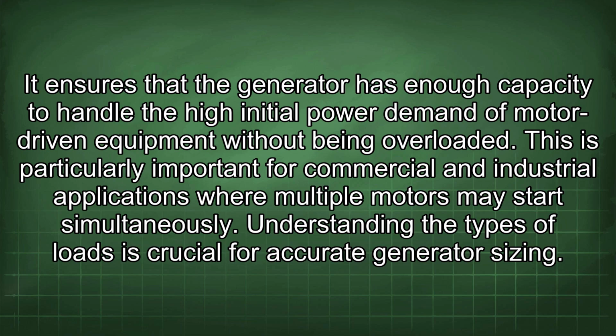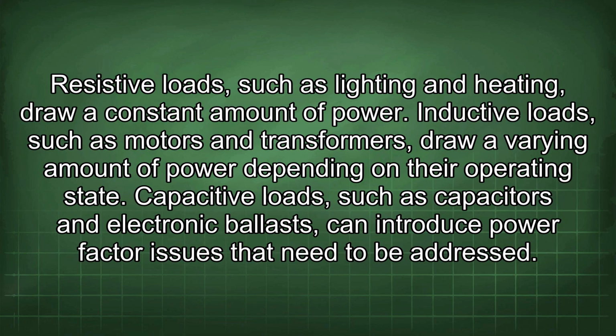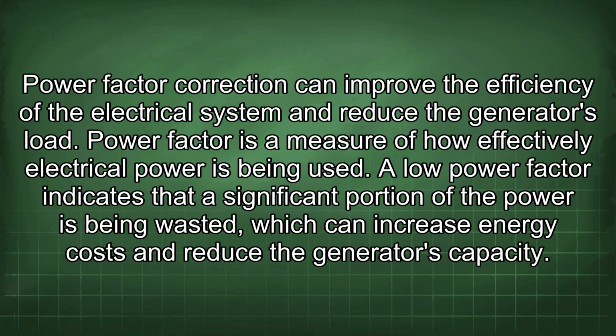Understanding the types of loads is crucial for accurate generator sizing. Resistive loads, such as lighting and heating, draw a constant amount of power. Inductive loads, such as motors and transformers, draw a varying amount of power depending on their operating state. Capacitive loads, such as capacitors and electronic ballasts, can introduce power factor issues that need to be addressed. Power factor correction can improve the efficiency of the electrical system and reduce the generator's load. Power factor is a measure of how effectively electrical power is being used. A low power factor indicates that a significant portion of the power is being wasted, which can increase energy costs and reduce the generator's capacity.